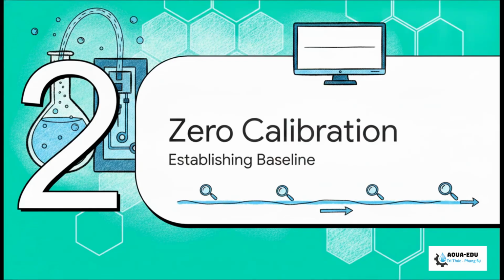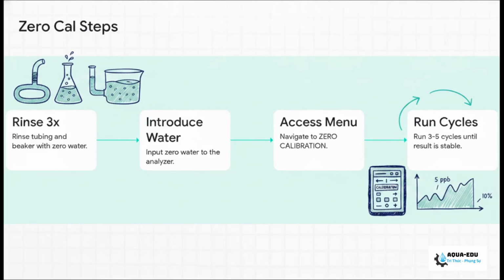Moving on to Section 2, Zero Calibration Process. Now, brothers, it's time to establish our baseline by running the zero calibration. This is basically where we tell the machine exactly what absolute purity looks like. Here is the exact sequence. First, rinse your tubing and beaker at least 3 times with zero water to strip away any environmental contamination. Second, introduce that zero water into the analyzer. Third, hit zero calibration on the menu. Finally, you're going to run 3 to 5 continuous cycles.